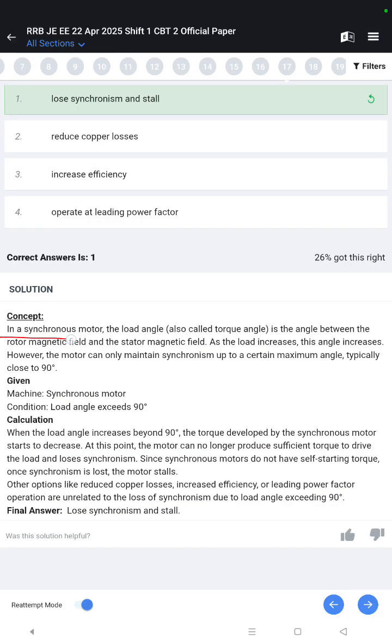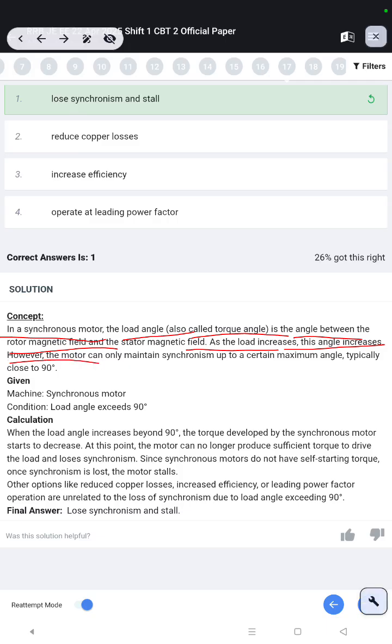In a synchronous motor, the load angle, also called torque angle, is the angle between the rotor magnetic field and the stator magnetic field. As the load increases, this angle increases. However, the motor can only maintain synchronism up to a certain maximum angle, typically close to 90 degrees.